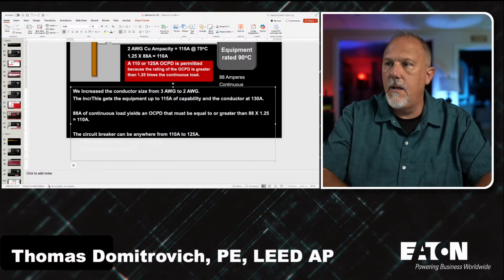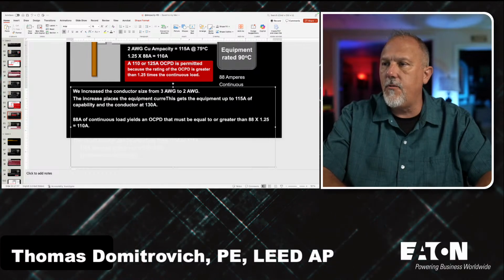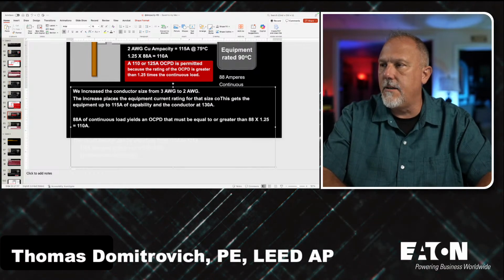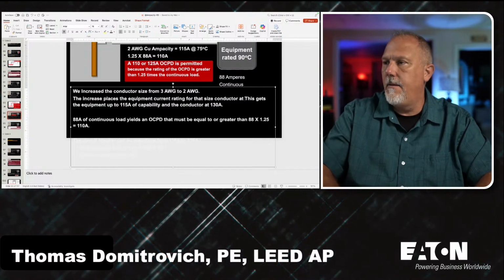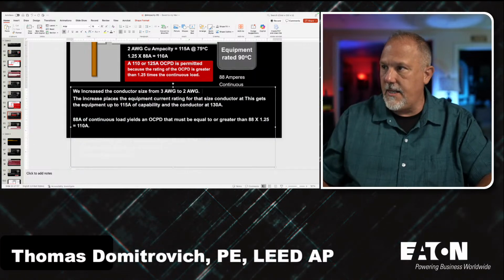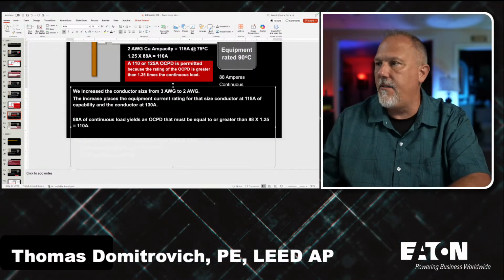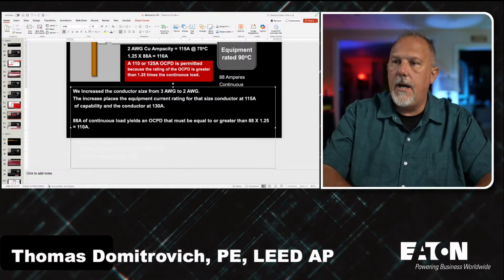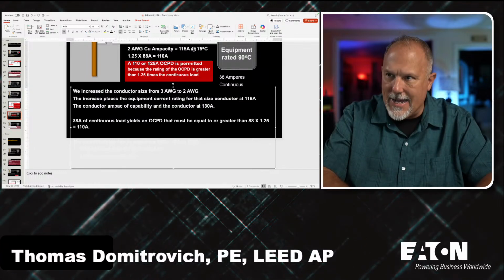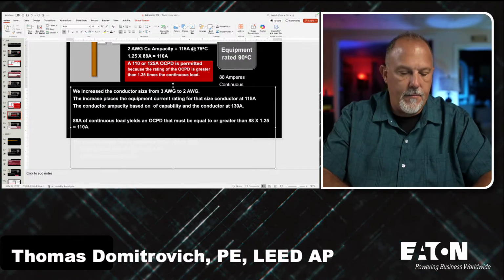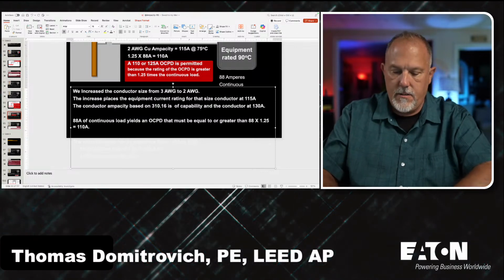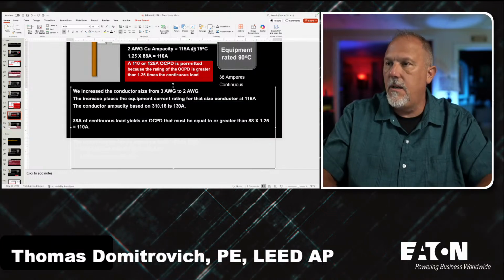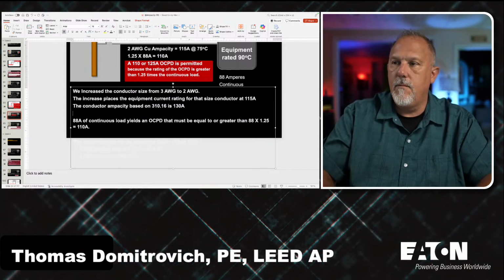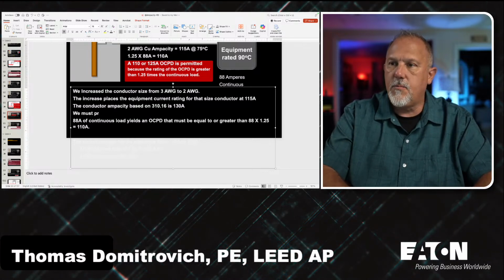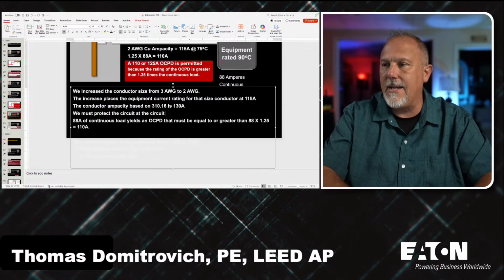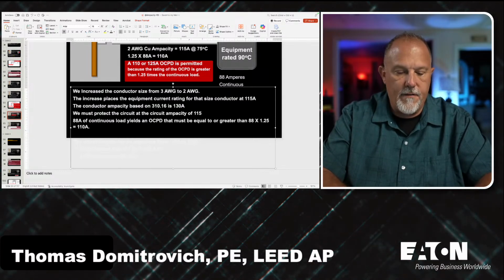The increase places the equipment current rating for that size conductor at 115 amps. The conductor ampacity based on 310.16 is 130 amps. We must protect the circuit at the circuit ampacity of 115 amps.